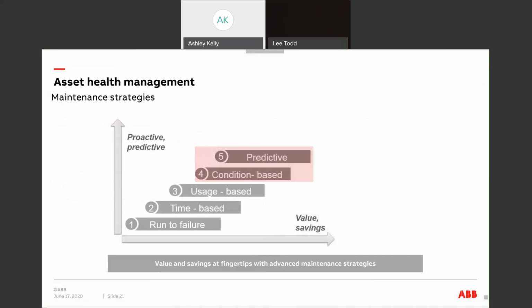So what are the maintenance strategies available to you, and what's the cost? You could run your site to failure and risk a total system loss—of course, none of you would do that. You could move up the ladder and go to time-based, which does not take into account if a breaker switched once or 300 times, or whether that occurred in 1 year or over multiple years.